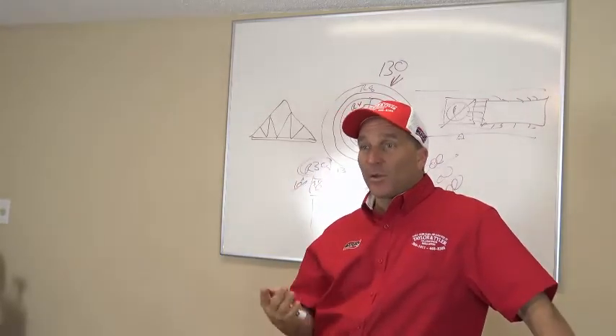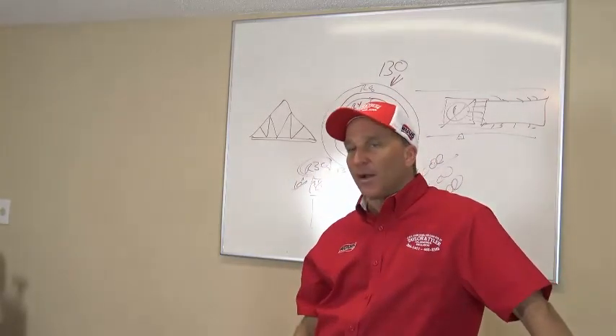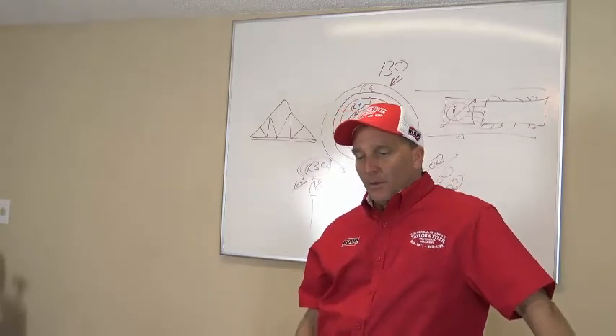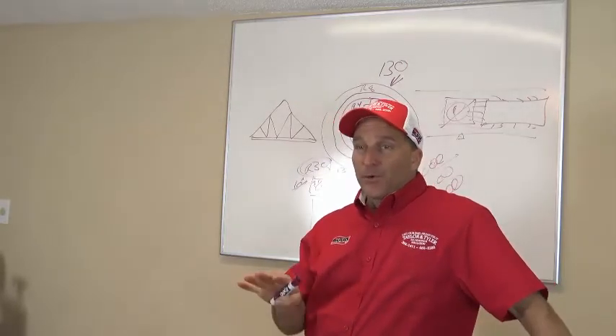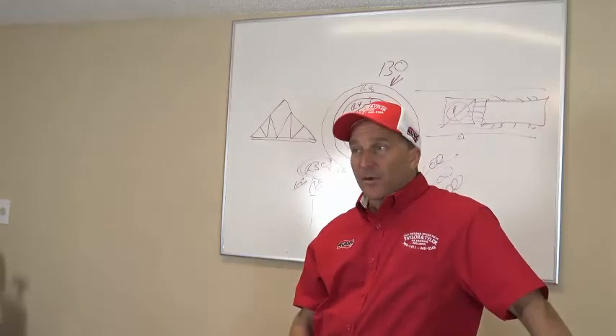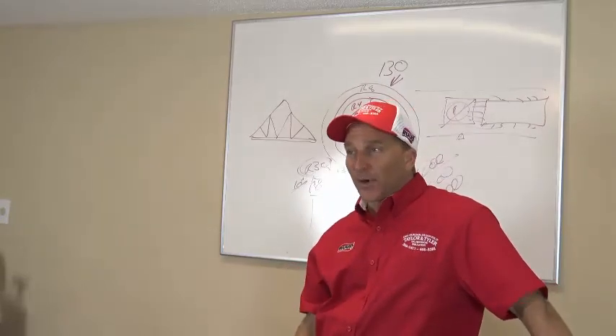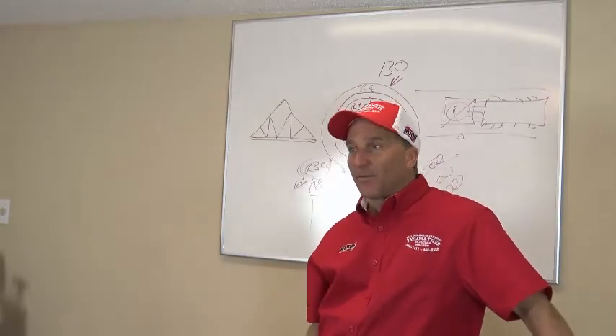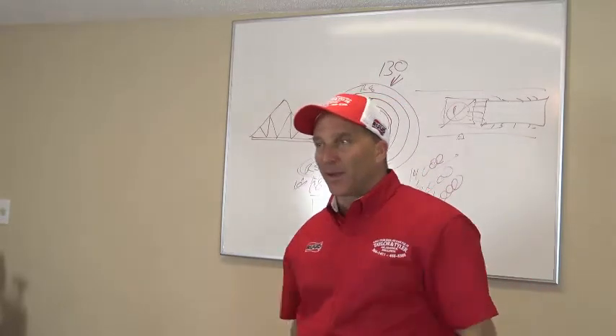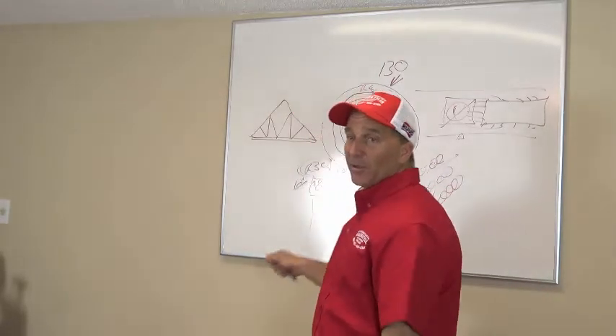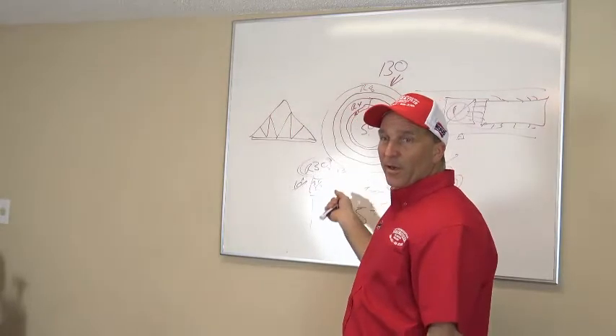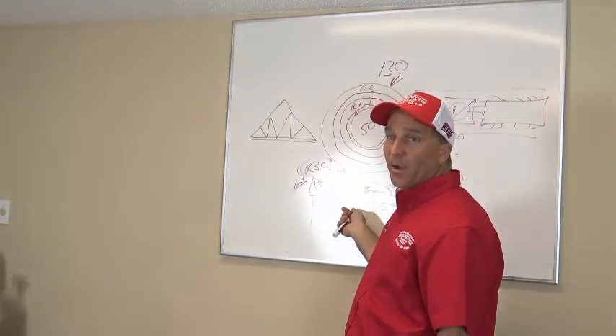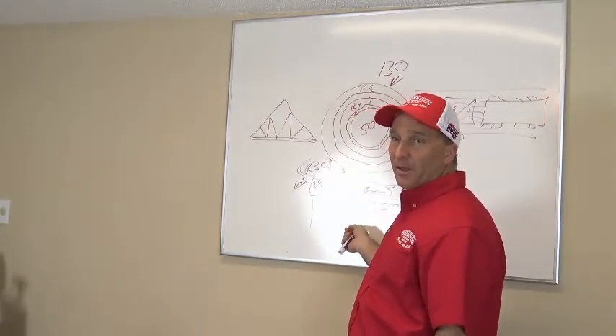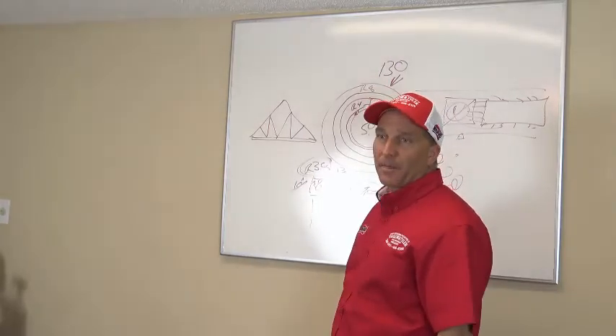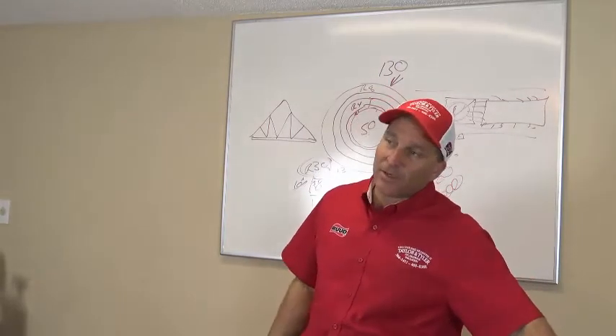I said, "Okay, the only thing that's not hooked up is that compressor, right?" He goes, "All right." I said, "Now, I'm going to prove to you that it's the compressor. So I'm going to only hook the compressor up." So I pulled the leads off of the fan motor and hooked the compressor back up. I said, "Now watch. When I plug the breaker back in, it's going to blow the breaker right away. So you want to watch?" Click, pow! I said, "Now, we're going to put a new compressor in, a new condenser in for you tomorrow.